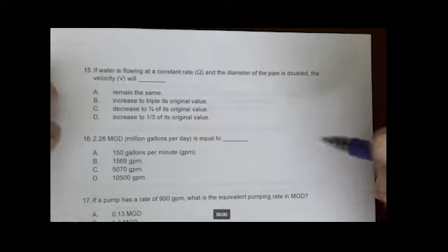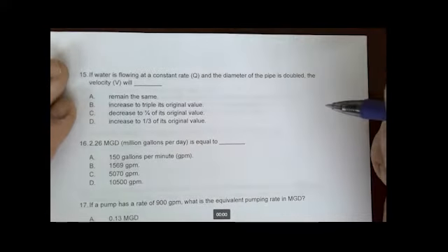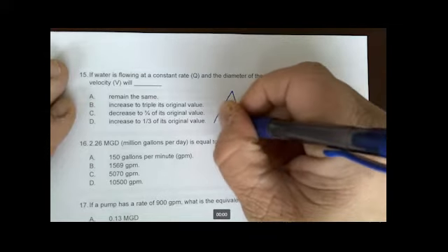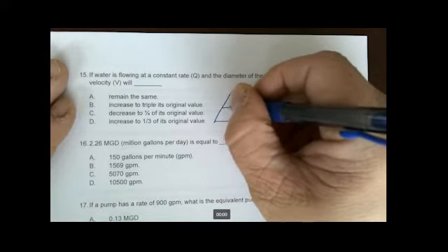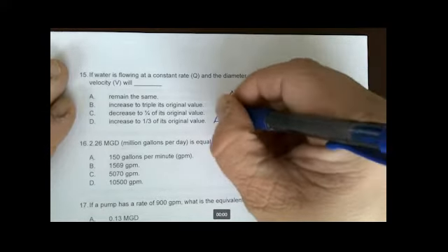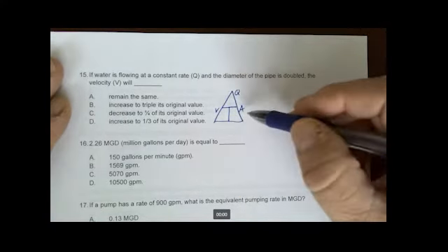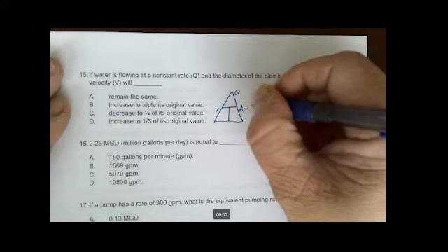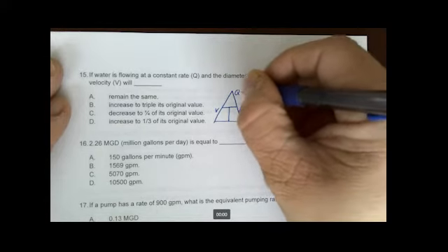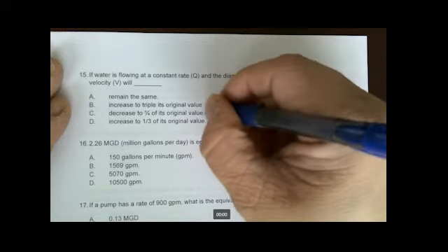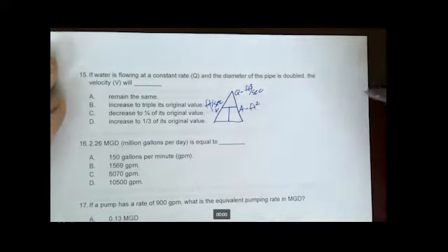Blank. All right, so in order to do this, we need the QVA equation, which I use a triangle for because it helps out. I call it the continuity triangle. And I put Q, V, and A. Q always has to be up top. It doesn't matter where V and A are. Well, A is always square feet. Q is always cubic feet per second. And velocity is always feet per second, okay?